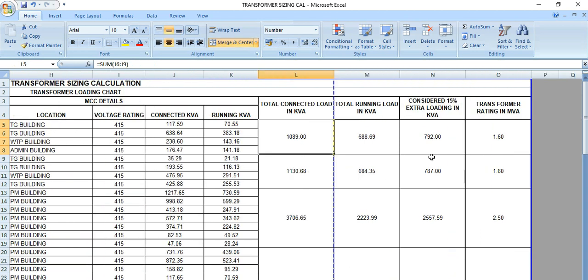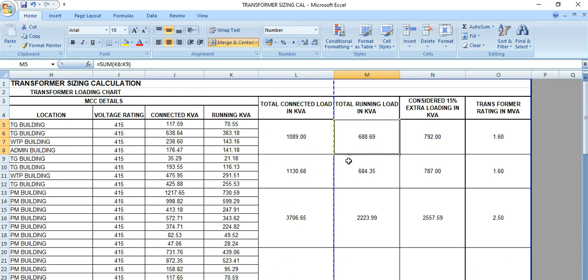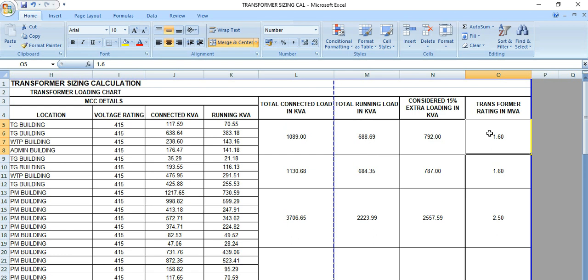And finally, what is the total absorbed load or the total running load for all the MCCs, three numbers, four numbers, five numbers MCCs, whatever may be. And considering that, we need to put some margin and then take the higher side. So here 1 MVA may be sufficient, but depending on the client's requirement, depending on the future requirements, we have considered this 1.6 MVA.